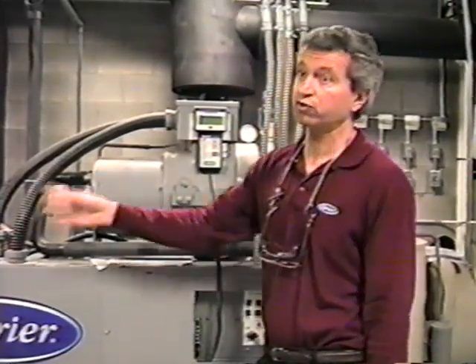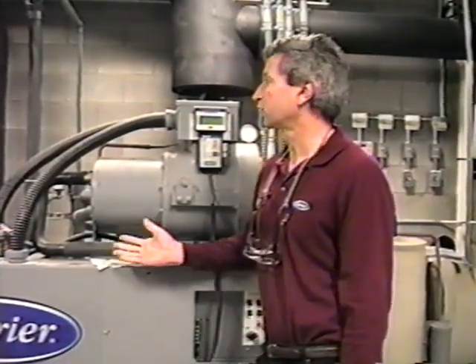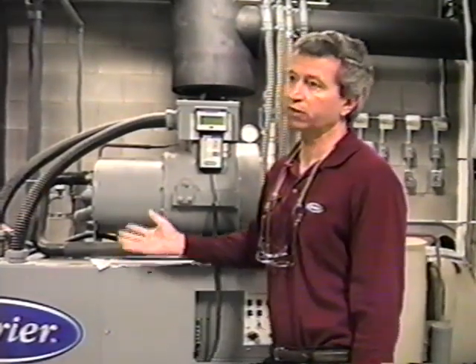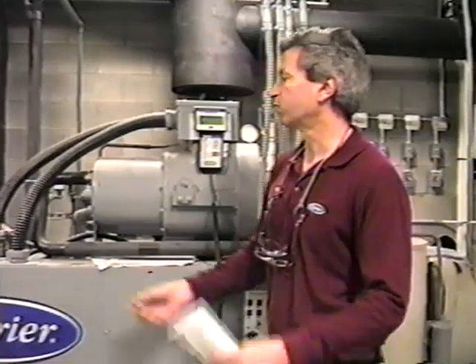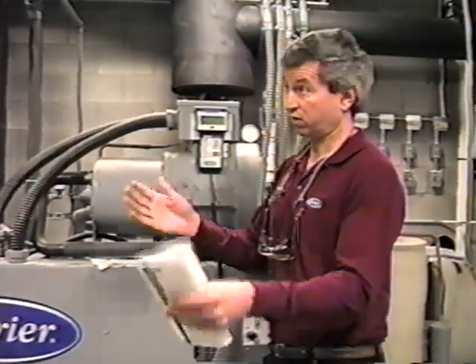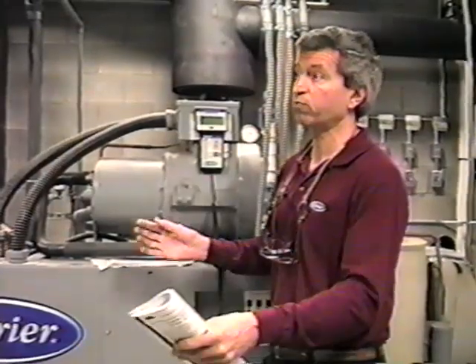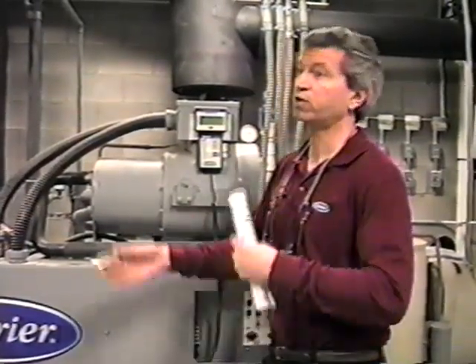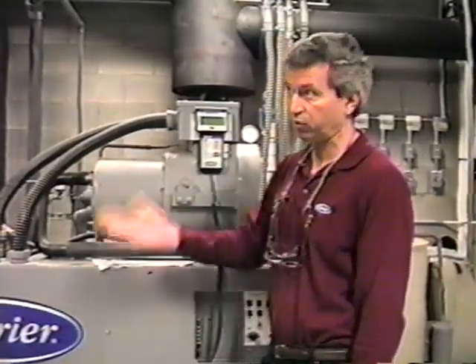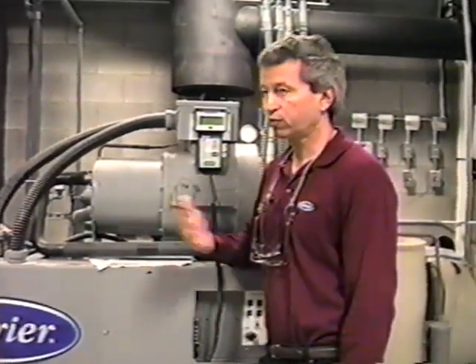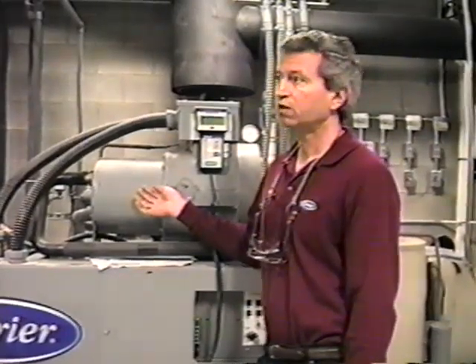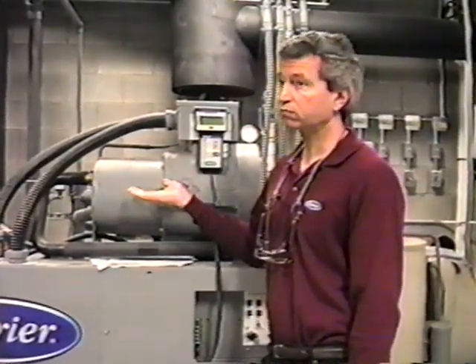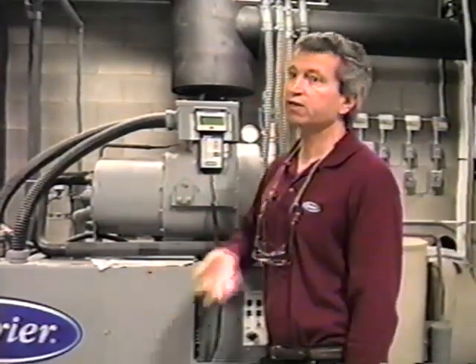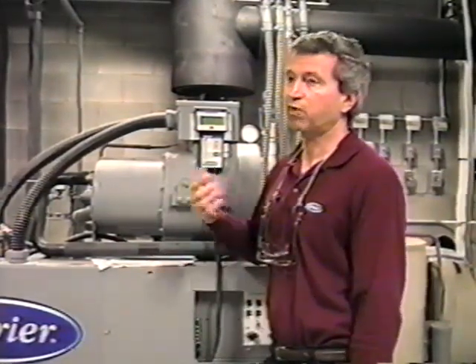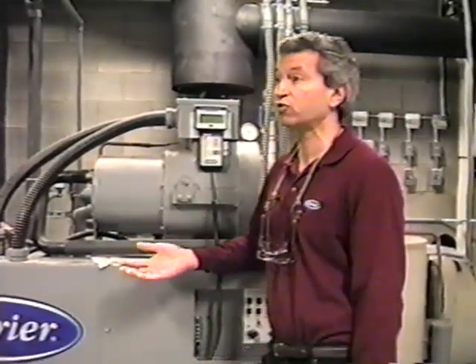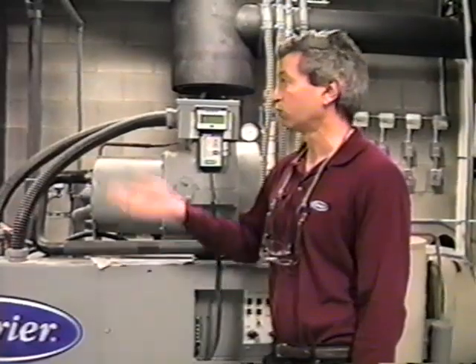You will have times when both circuits do operate. This started up when you had about a 20-degree brine, so it's going to try to pull down to 15 degrees. With a microprocessor control, it's going to look at your varying conditions as far as your entering brine and your leaving brine and determine over a period of time how much capacity is required to pull it down to 15. So when it first starts up, you're going to run on the one compressor. The one compressor will load up fully. Again, if the pull down rate isn't sufficient and the processor decides that it's a substantial amount of capacity to pull it down to that 15, it will start the second compressor.